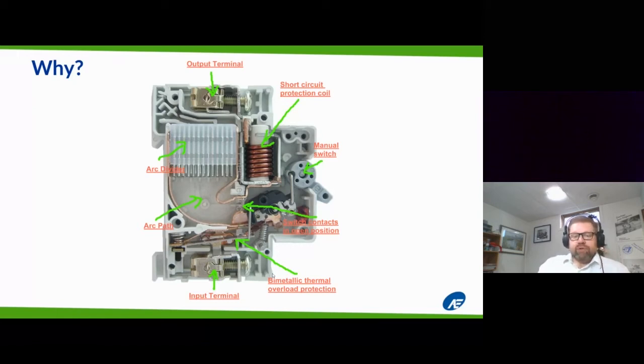Now the key part here is something called a bimetallic thermal overload protection. There's the springs, and then there's the short circuit coil. So the two things that are going to fail here are that bimetallic strip and that spring. If either of those components get relaxed or fatigued in their position, they're not going to work as intended. They're not going to suddenly fail. They're not going to suddenly release. They might, but they're not going to work when you want them to.